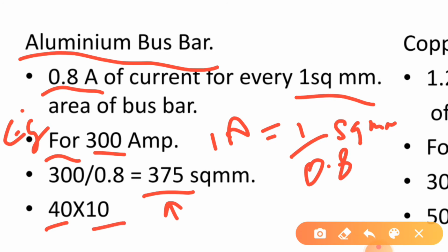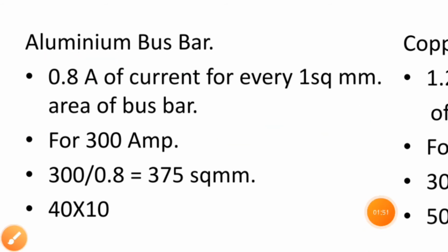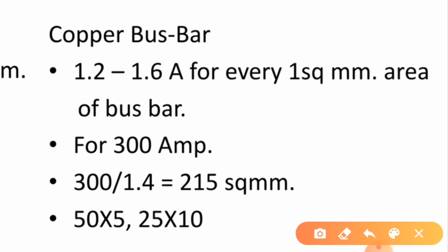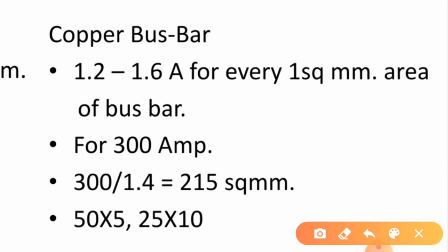So friends, this was the calculation for aluminium bus bars. And friends, here I want to make a note that this is not the perfect calculation of bus bars. We take other factors like fault current, temperature, etc. But these are the thumb rules which are generally taken by control panel manufacturers for bus bar calculations.